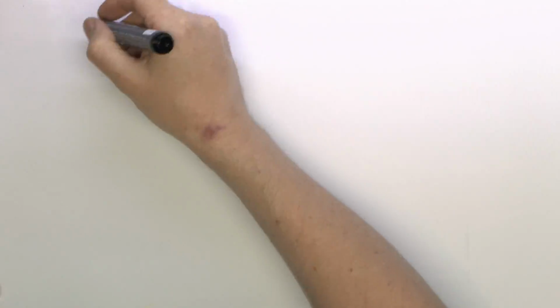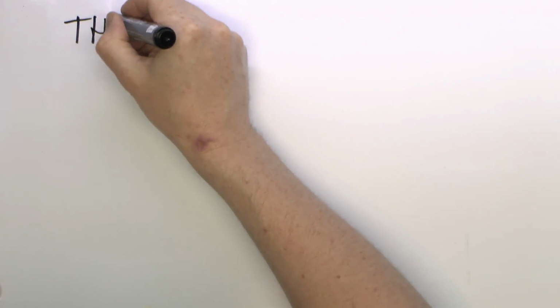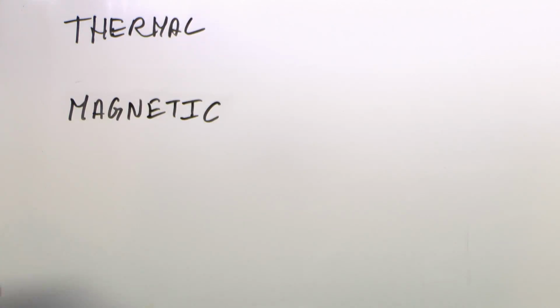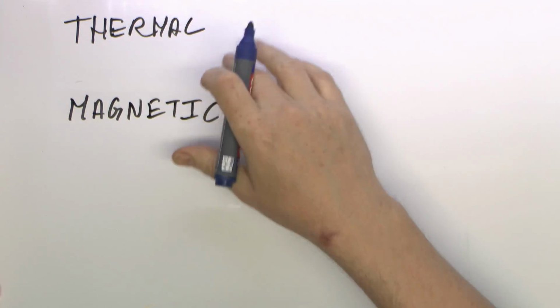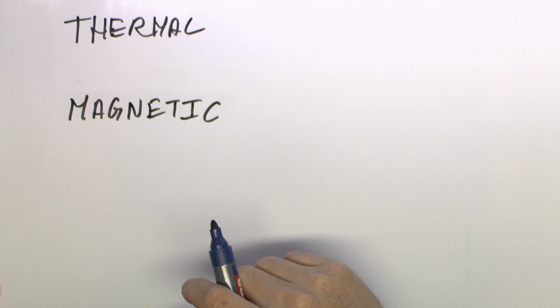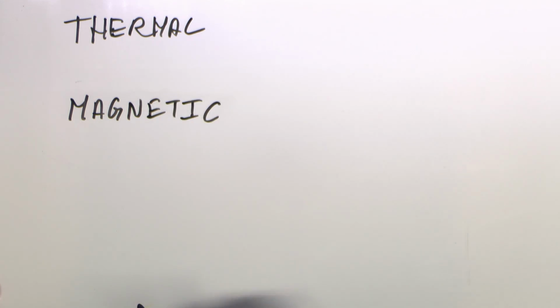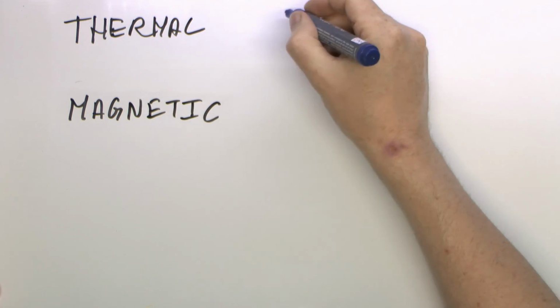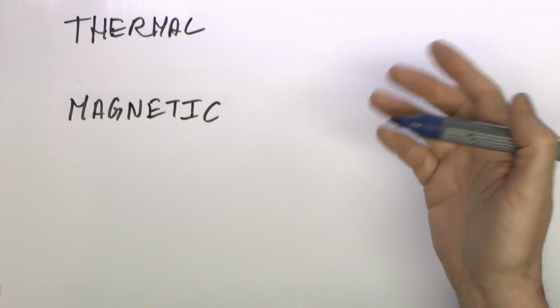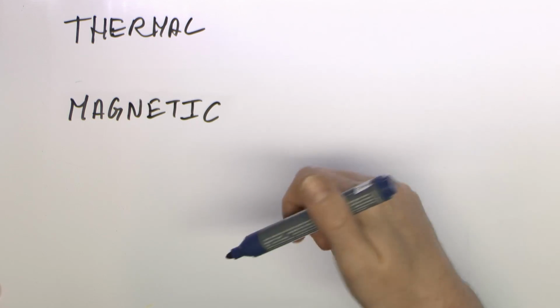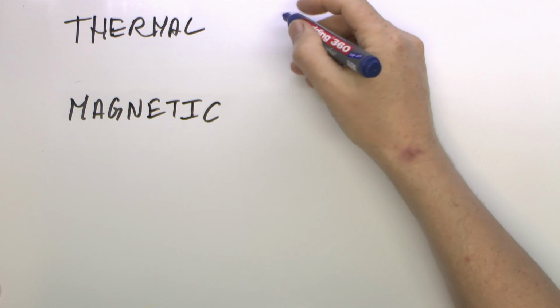Now, I've seen circuit breakers in previous videos, including what's actually inside them, and circuit breakers contain two separate elements inside, and these are thermal and magnetic. The thermal part is usually a bimetallic strip, and that only reacts to moderate overloads, and basically that's the strip which will slowly bend as it heats up. Once it gets to a certain temperature, it will then trip the circuit breaker.